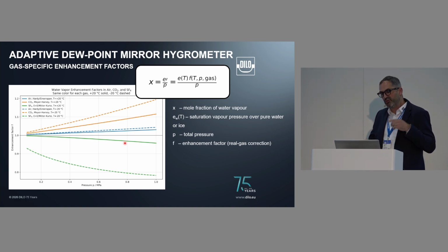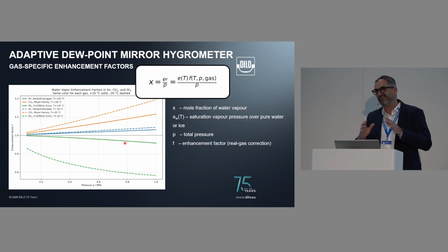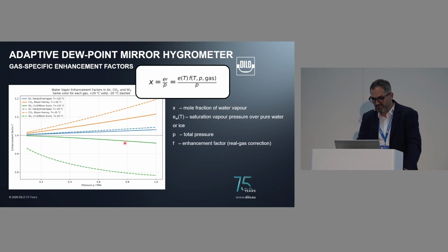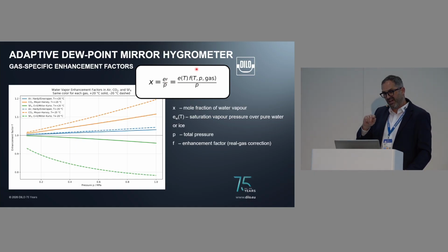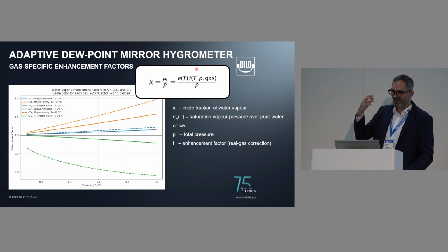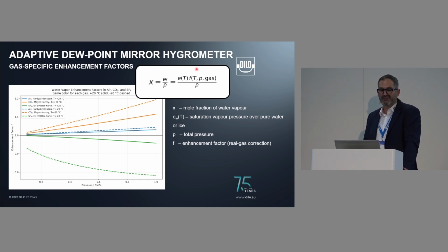For example, if you measure in different gases and at increased pressures, your water vapor pressure no longer behaves ideally. So you have to correct it with a real gas correction factor, and we call this the enhancement factor. By knowing the gas type, you can implement those enhancement factors and directly show on the display of your instrument the best value you can get, let's say.